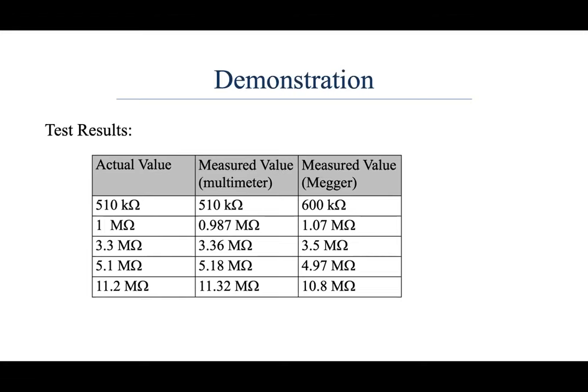How important is accuracy, would you think, when it comes to measuring the resistance value of the insulation and knowing if there's a problem? I don't think it's highly important to get a very accurate number when you're talking about the difference between 10.1 and 10.5 megaohms. You know, you're still up there at the high range. So as long as you can prove that it's got a very high resistance, accuracy isn't quite the most important part. Thank you.